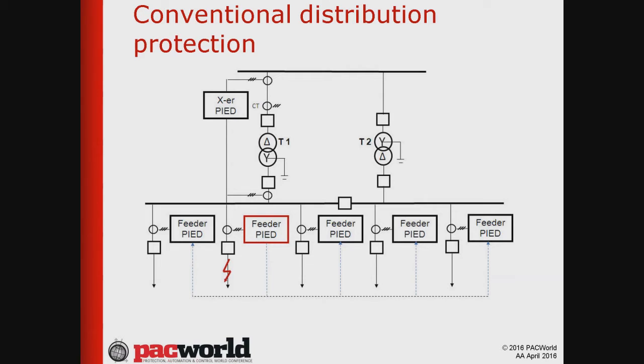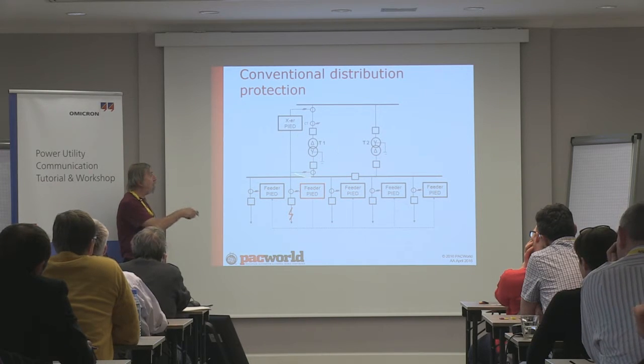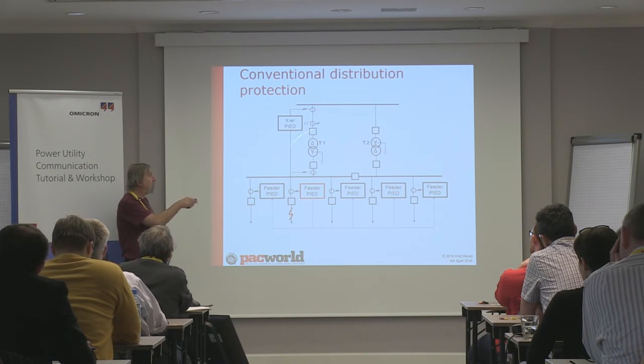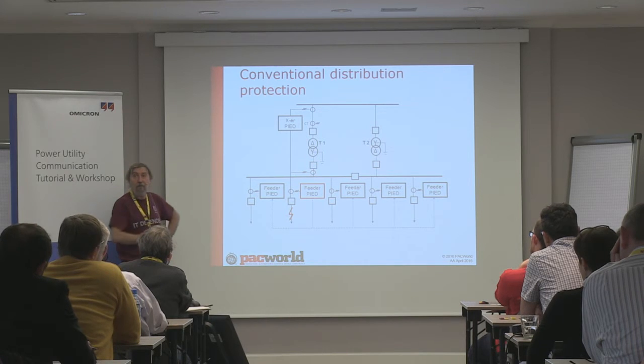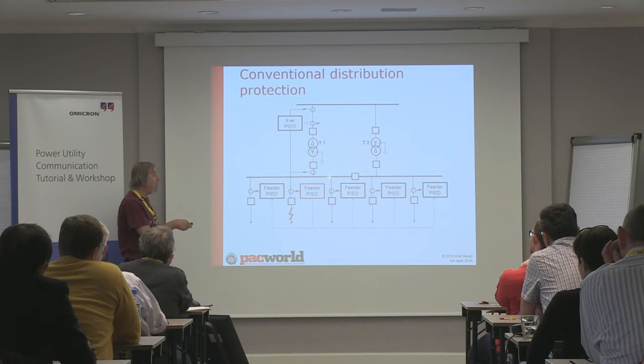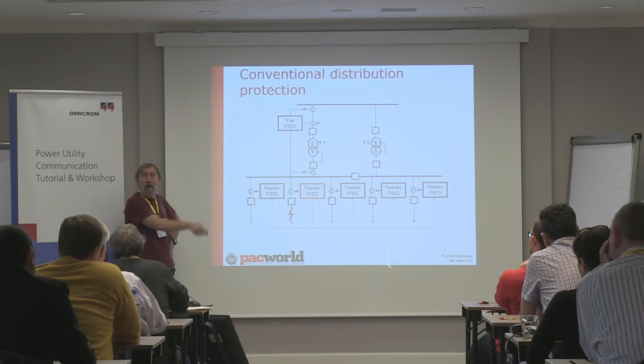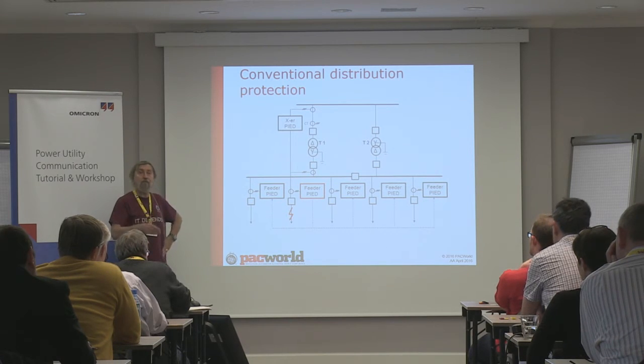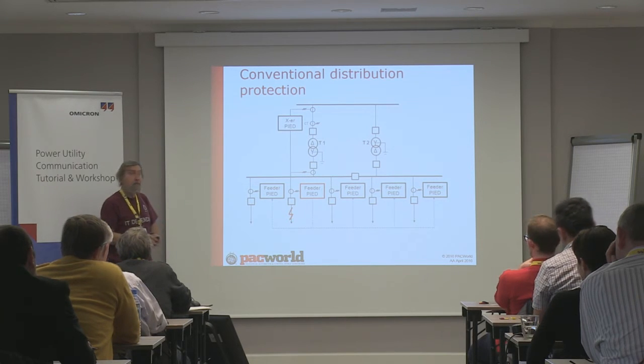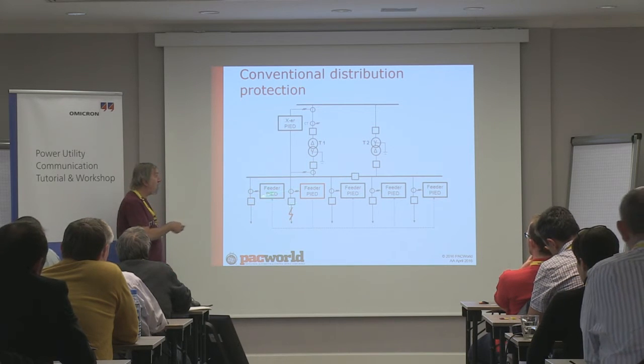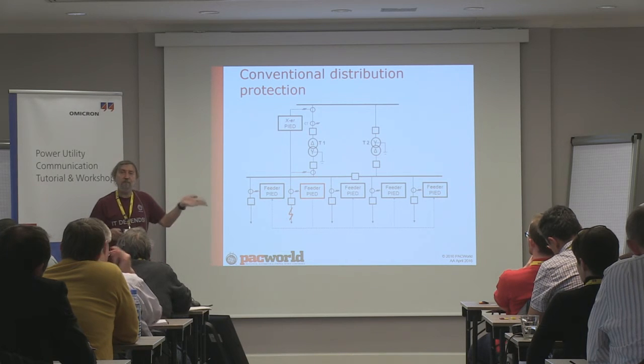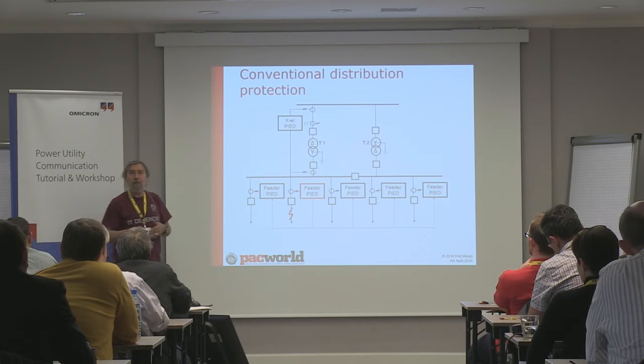When we go to the distribution level, there are a lot of protection schemes that we traditionally use that are based on coordination of the inverse time overcurrent protection of the transformer and the feeders. So for example, if I have a fault on this bus and we have no bus protection, it is going to be cleared by the backup protection of the transformer with a time delay. The problem with this is that this time delay is going to result in a voltage sag that is going to be experienced by the wind generators on the healthy part of the distribution system, resulting in their loss because of the ride-through characteristic. This is why we try to improve the fault clearing time by using a communications-based message scheme, something that different people call different names. Some people call it inverse blocking.